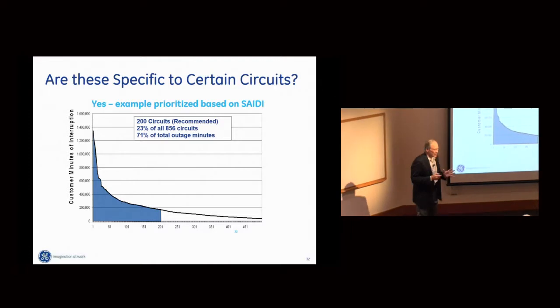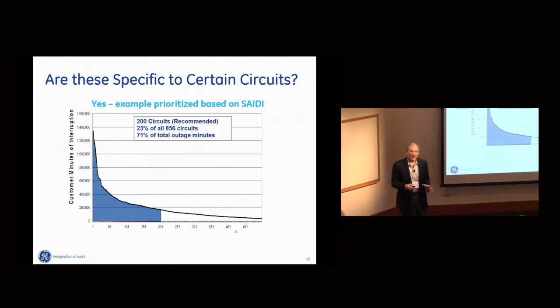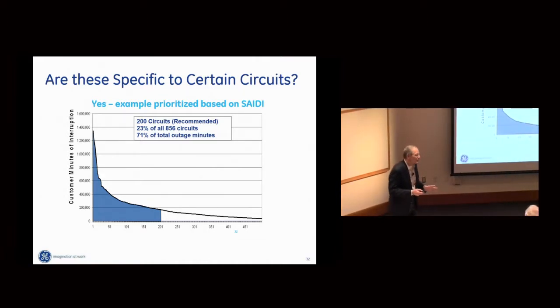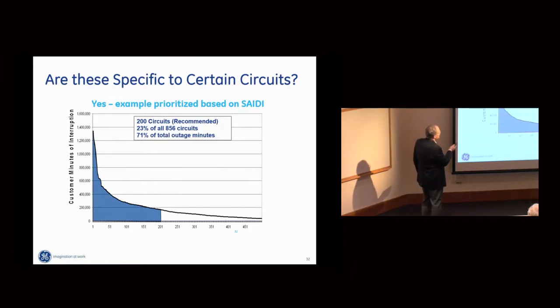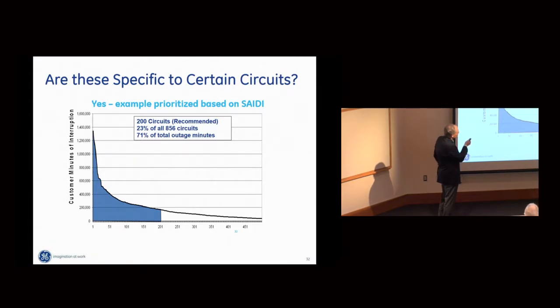Here's another important point: I don't have to implement fault detection, isolation, restoration logic on every single feeder. I study my feeders — in this example, the utility we studied had 856 circuits. Initially you'd think you need FLISR on all 856, but it turns out that 23% of those circuits, about 200, are responsible for 71% of the total outage minutes. Be smart about what we're doing — help the customer, spend money wisely, and get the biggest bang for the buck. So I implement the technology on 200 circuits but still cover 71% of the total outage minutes.